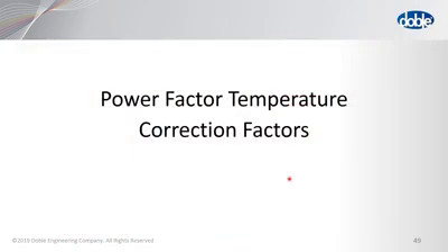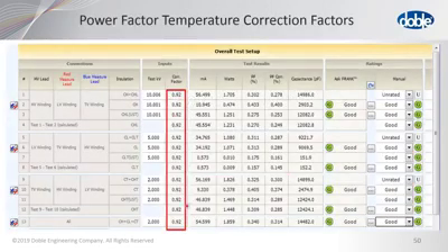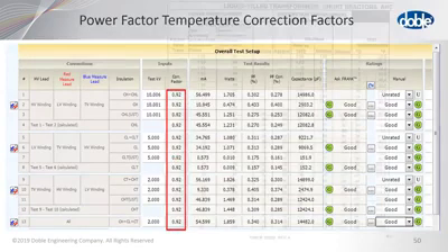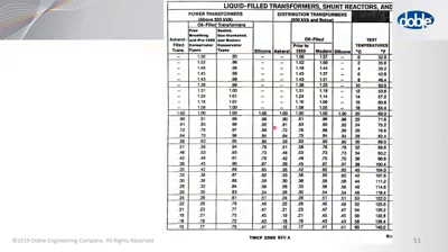Now, the power factor is corrected for temperature, related to, of course, the temperature of the apparatus and the kind of preservation system that the transformer has. I'm going to explain how that works. Here is the correction factor for an example test, and it's 0.92. Now, where does that number come from? Well, previous to the DTA software, we used to publish this chart or table in paper form, and I've just put it in this presentation so you can see where it came from historically and how it's used in DTA.